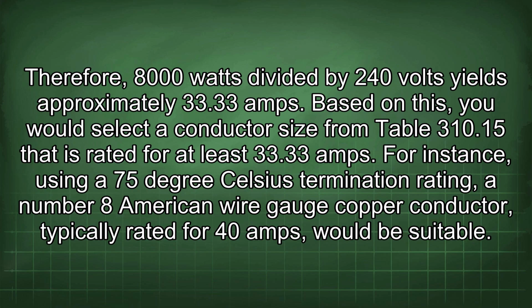Based on this, you would select a conductor size from Table 310.15 that is rated for at least 33.33 amps. For instance, using a 75 degrees Celsius termination rating, a number 8 American wire gauge copper conductor, typically rated for 40 amps, would be suitable.